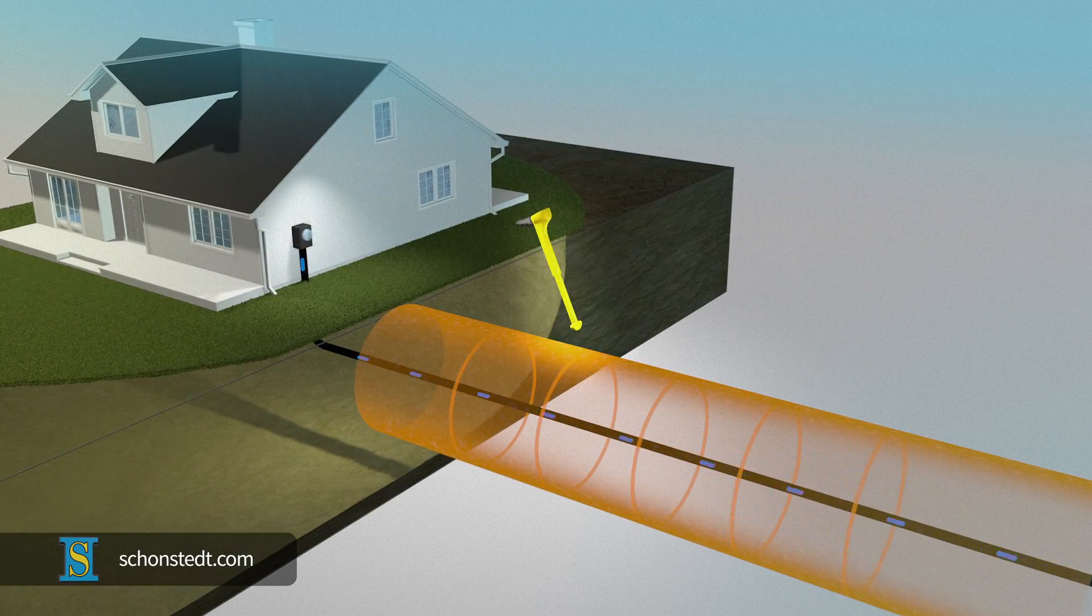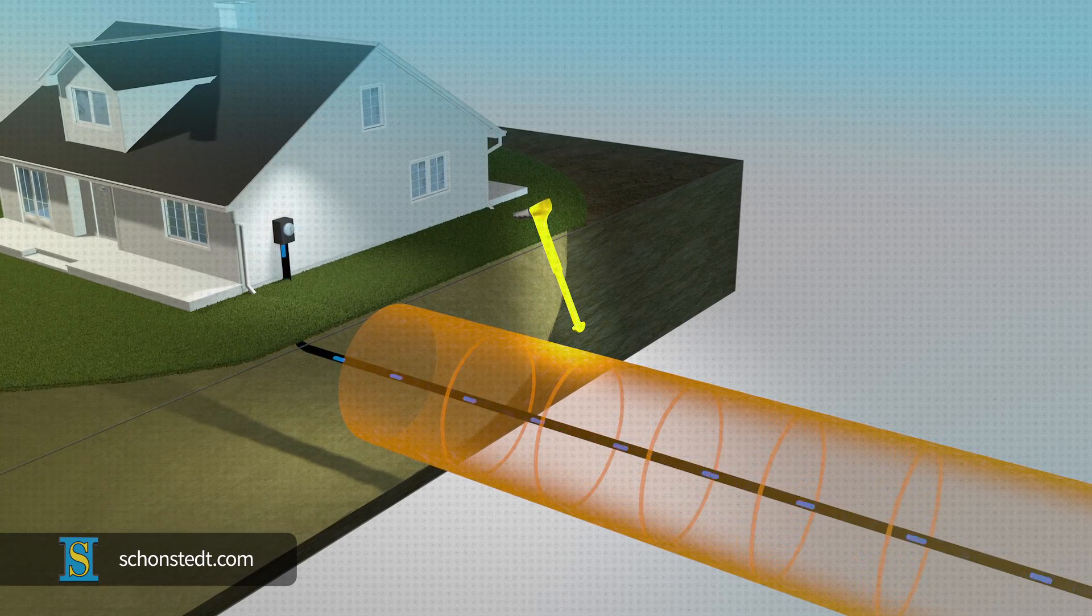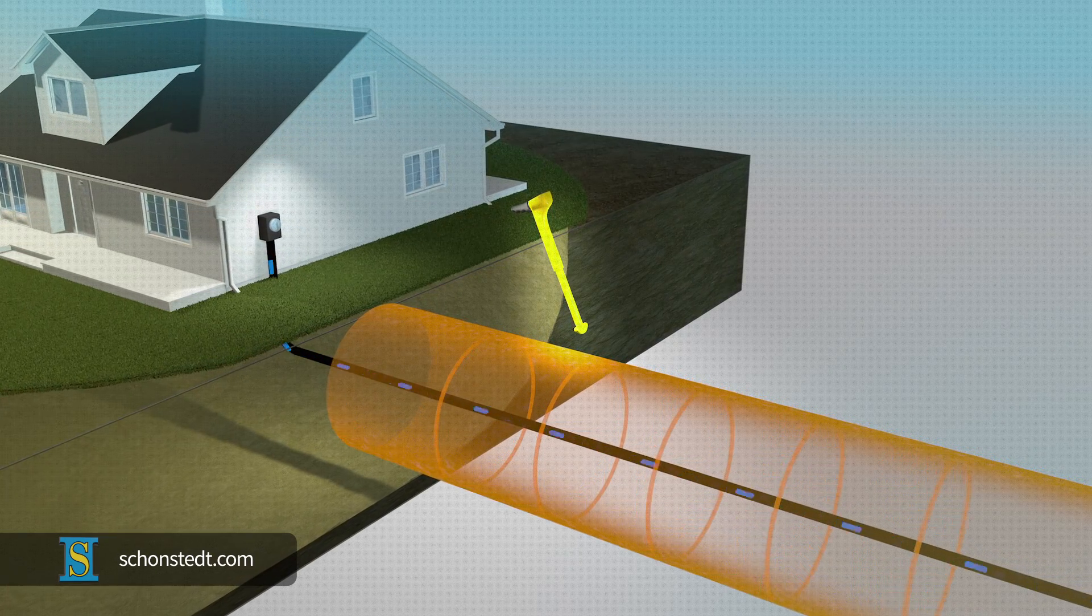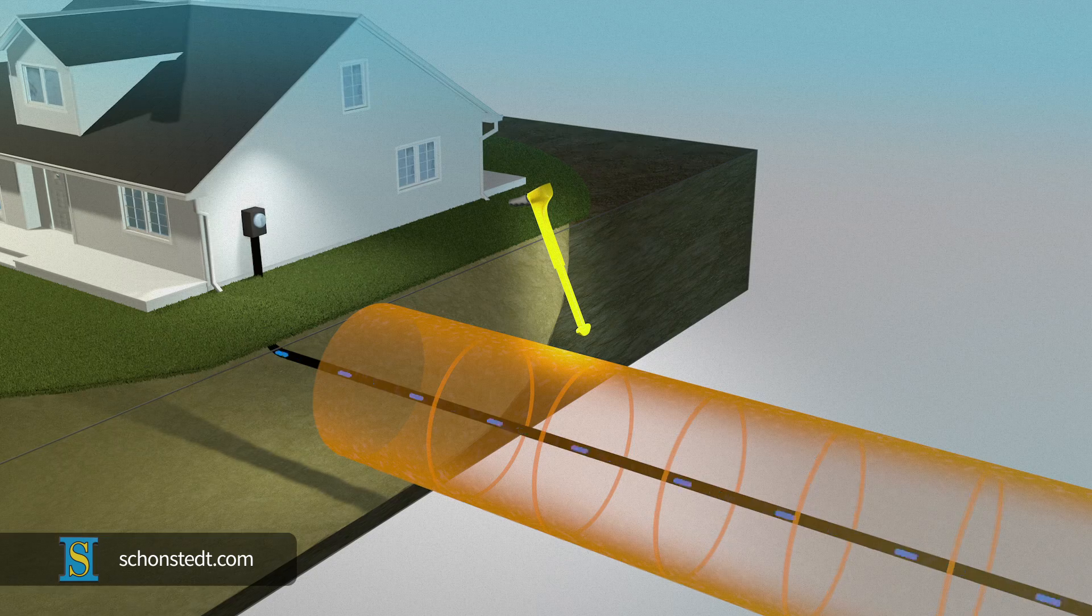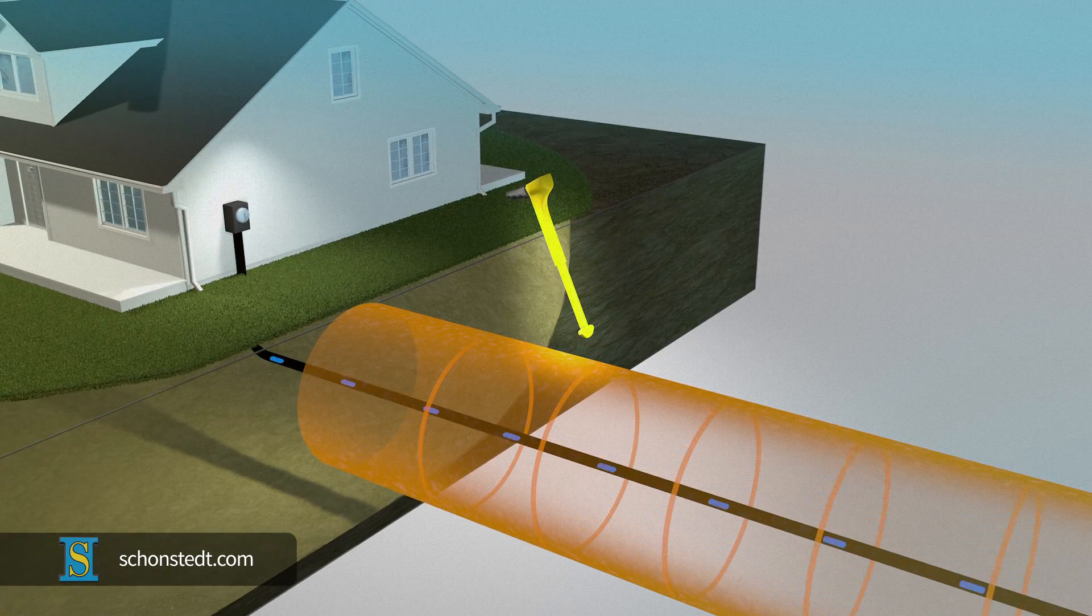The second method is known as passive locating, because the receiver detects a field created by the current that's already circulating on the cable. No transmitter is required.